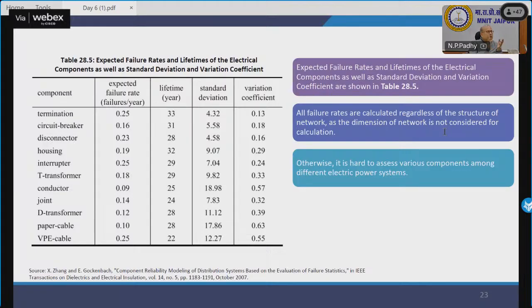Analysis based on 120,000 data samples has been obtained across the world for different devices. Based on these statistical histories, we learn the lifetime, the number of failures, and how frequently they fail. So for a given electrical distribution system or smart grid, I can conclude which components require more attention, and the system can be maintained accordingly. Instead of randomly deciding maintenance, we have a mathematical calculation based on historical data, from which the failure structure is derived and maintenance priority is designed.